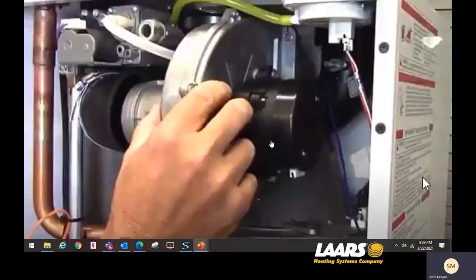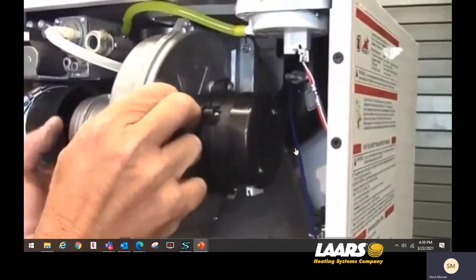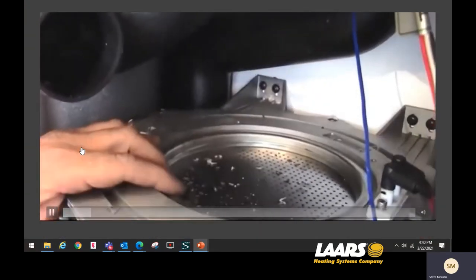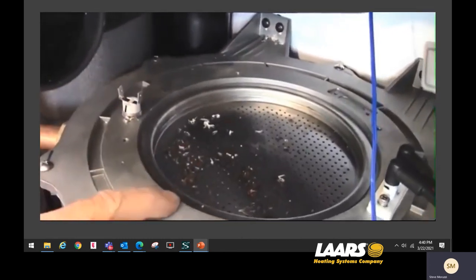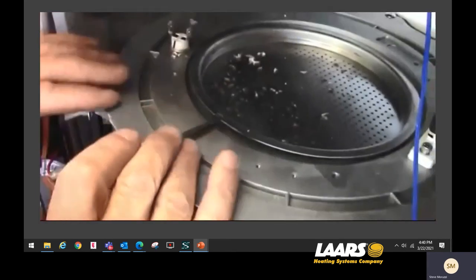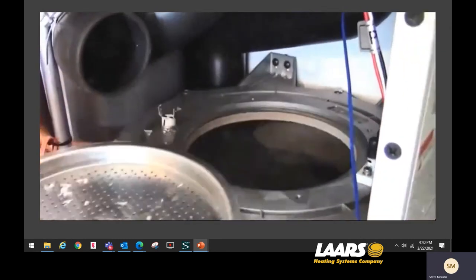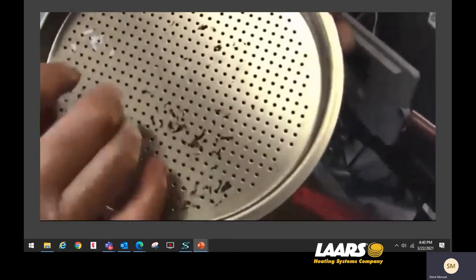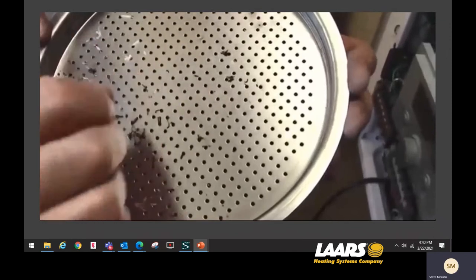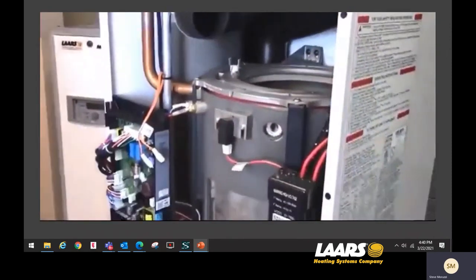To access the burner, pull the blower and arm out of position — we do have a separate video showing the full process. Removal of the burner plate is best done with a small screwdriver. There is a notch in the very front of the burner plate — insert the screwdriver into that notch and lift the burner plate out from the top of the boiler. Here you can see PVC shavings, some not burnt off and some that started to melt. They will plug the orifice holes and you won't get proper firing, so be sure to check this, especially for error codes 10 and 11.